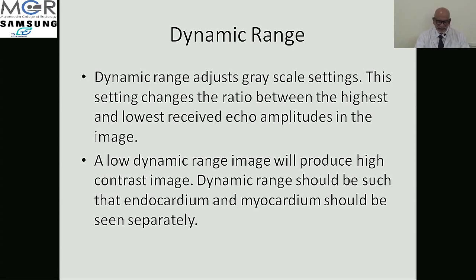A low dynamic range image will produce a high contrast image, which will look very nice, all blacks and whites, very crispy images. But with this you will lose very important intermediate shades, like endocardial shades, and shades produced by clots, which may be lost and you may never know whether they really exist there or not. So the proper maps should be selected. How should the dynamic range be? It should be such that endocardium and myocardium can be seen separately. Rather than seeing crispy images in black and white, you should get a map able to differentiate the softer images created by the endocardium and myocardium, and separate them.